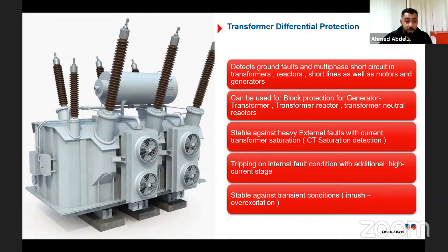So this is the condition, or phenomenon, or whatever you want to call it. We can call it security: our protection system is very secure against external faults or against normal operation with heavy load. And the second main characteristic of the protection system is that it should be selective. What does selective mean? It should trip in the case of an internal fault. So I should also have my protection system be very selective.